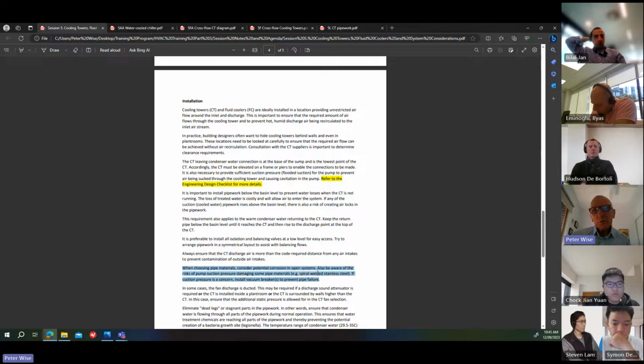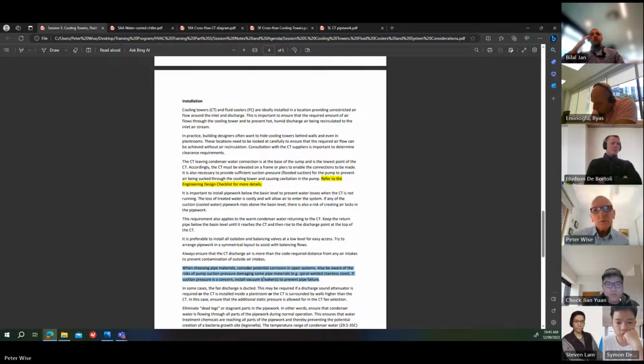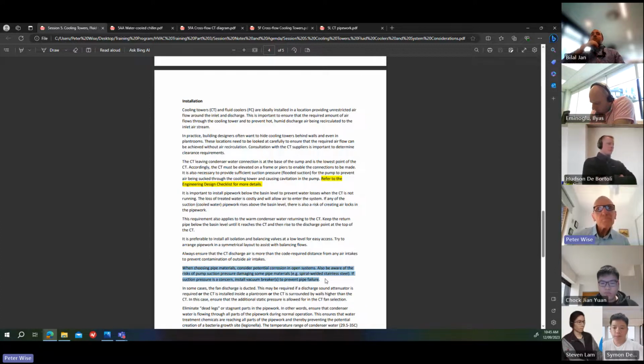Sometimes people use spiral welded stainless steel, which is a cheap form of stainless steel. It is less expensive, but you've got to be very careful on the suction side to avoid implosion of the pipe. If the system's looked after properly, this won't happen. But I have experienced it more than once, where someone's come to maintain a cooling tower and they've closed the suction valves without going to turn the pumps off. So in designing it, you've got to try and prevent this happening.